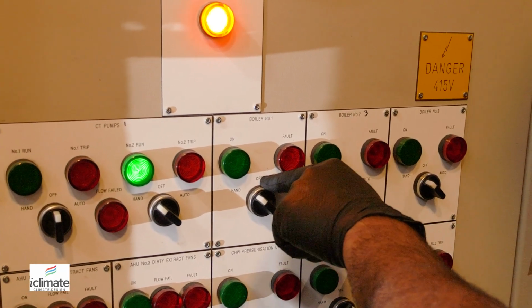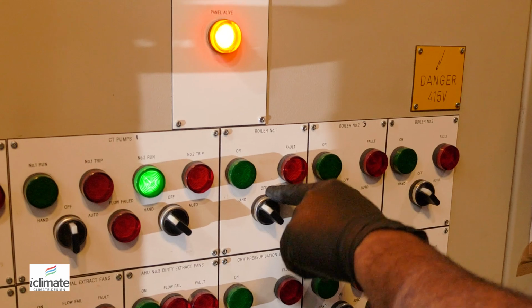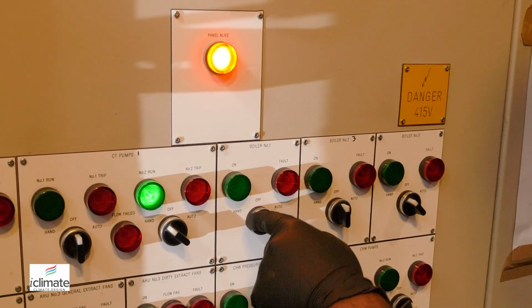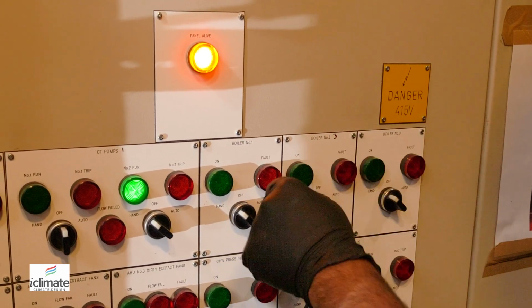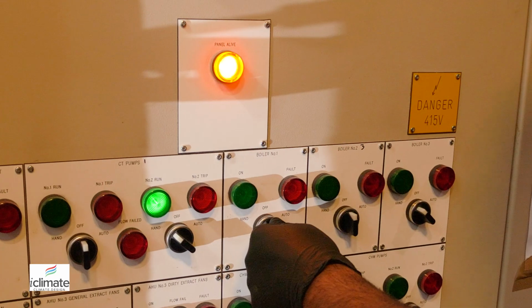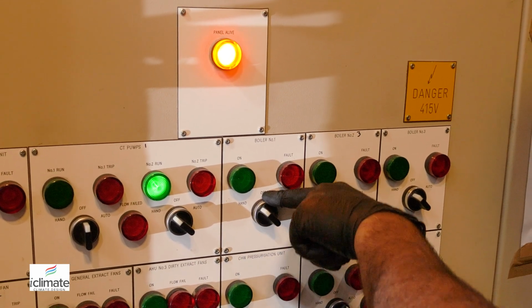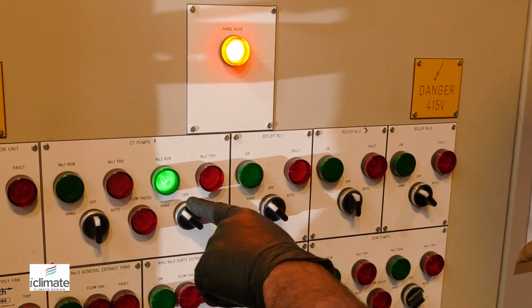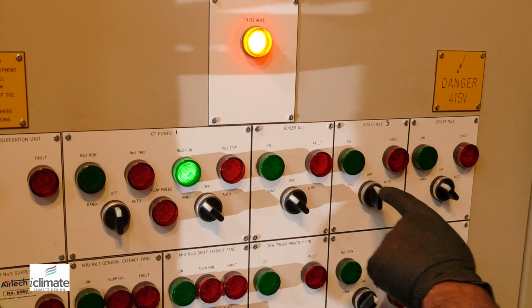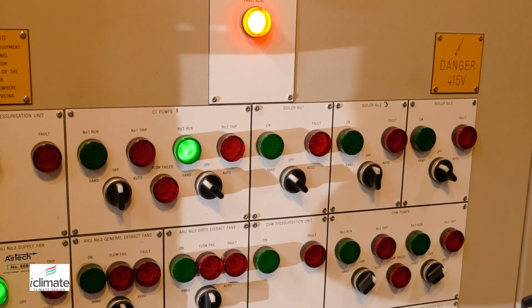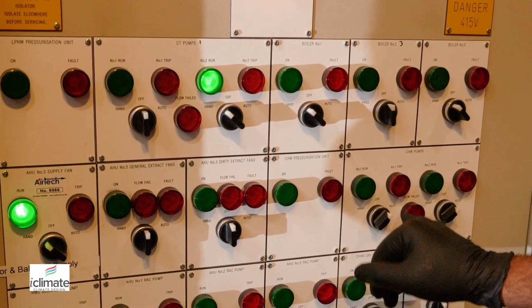You've got an off in case you need to turn something off and isolate it from the BMS and locally, and it's got a hand. Hand means that you want it to run right now. It's a manual override, right? So as you can see, boiler one's on hand. You can see the CT pumps, what we're hearing right now, is on hand. Nothing is on auto because the BMS needs to be updated, right? So we've got numerous lights out.